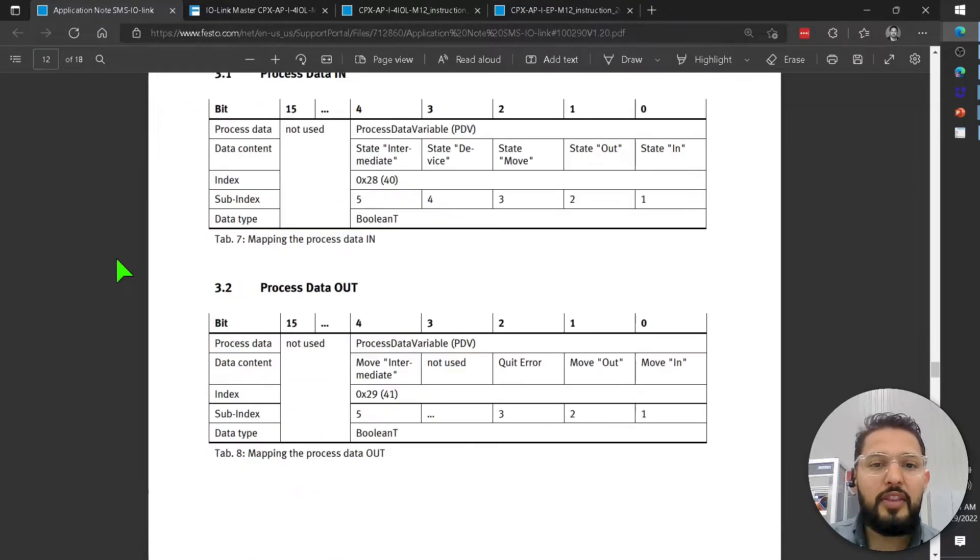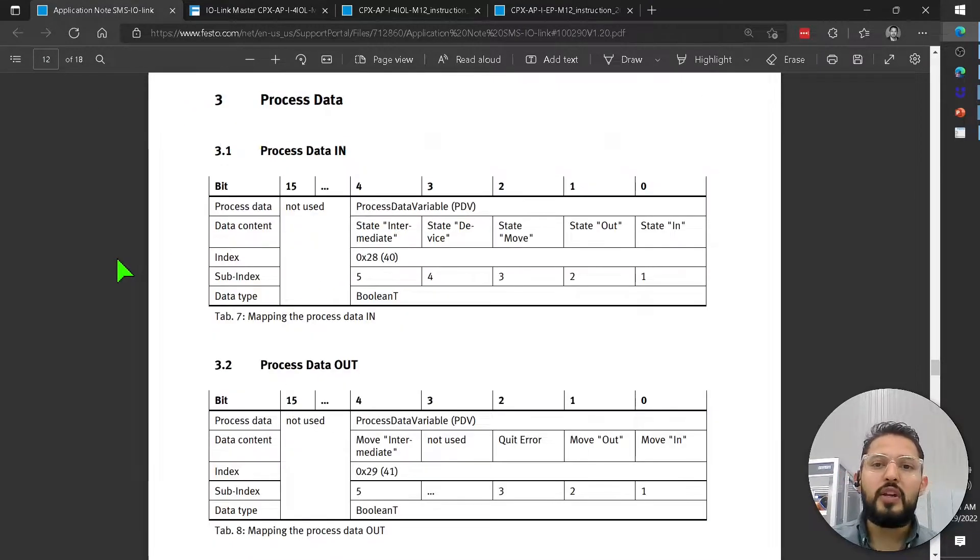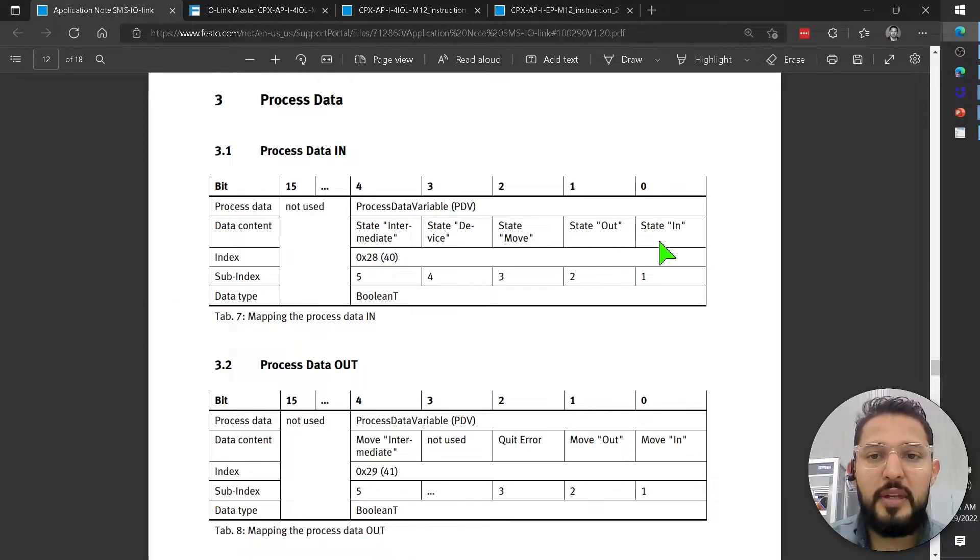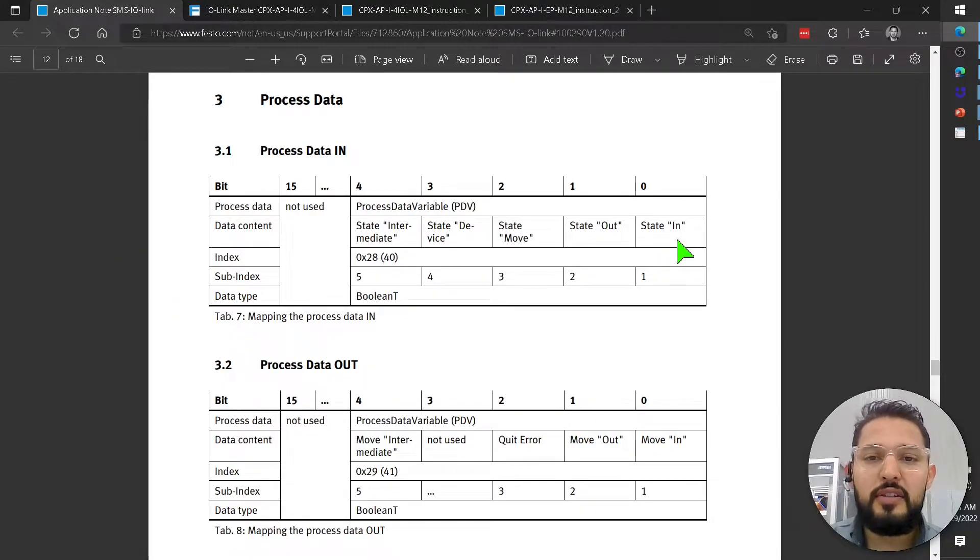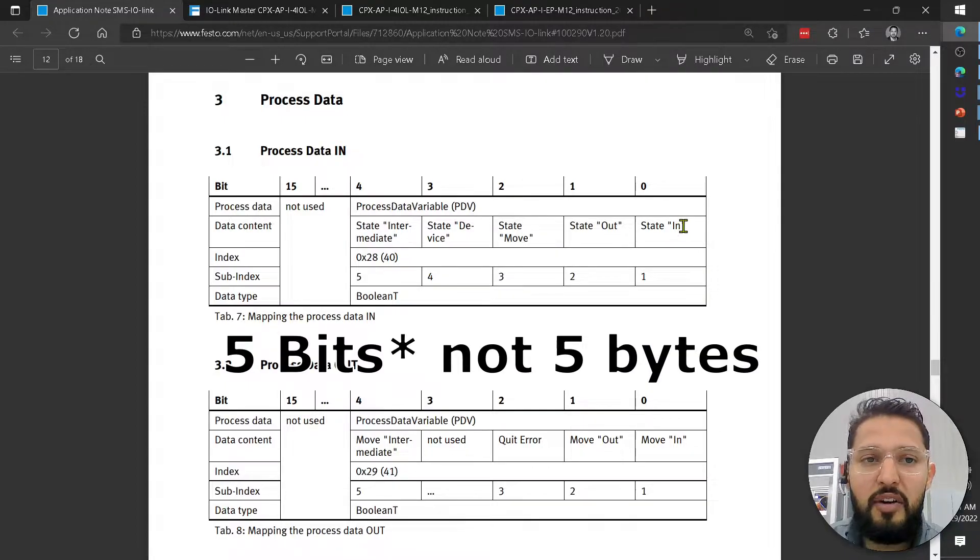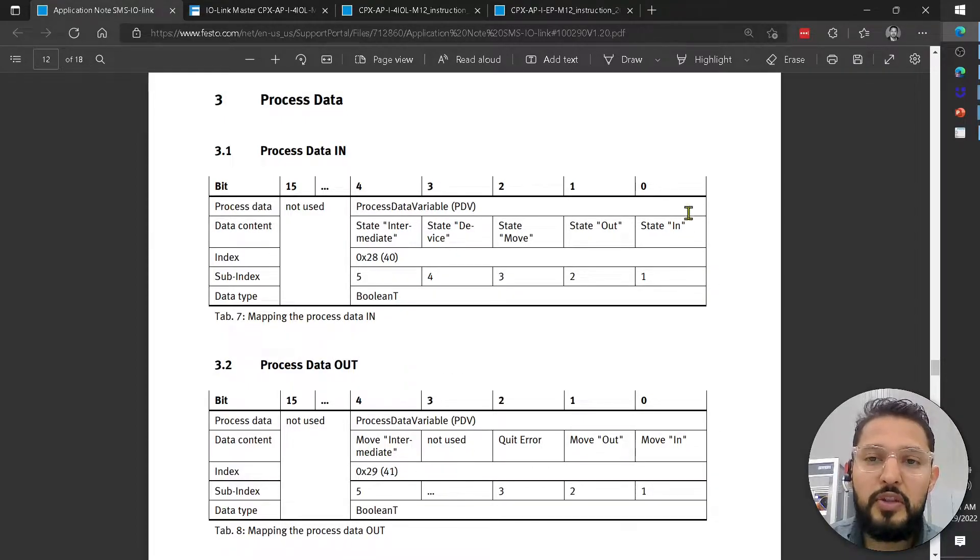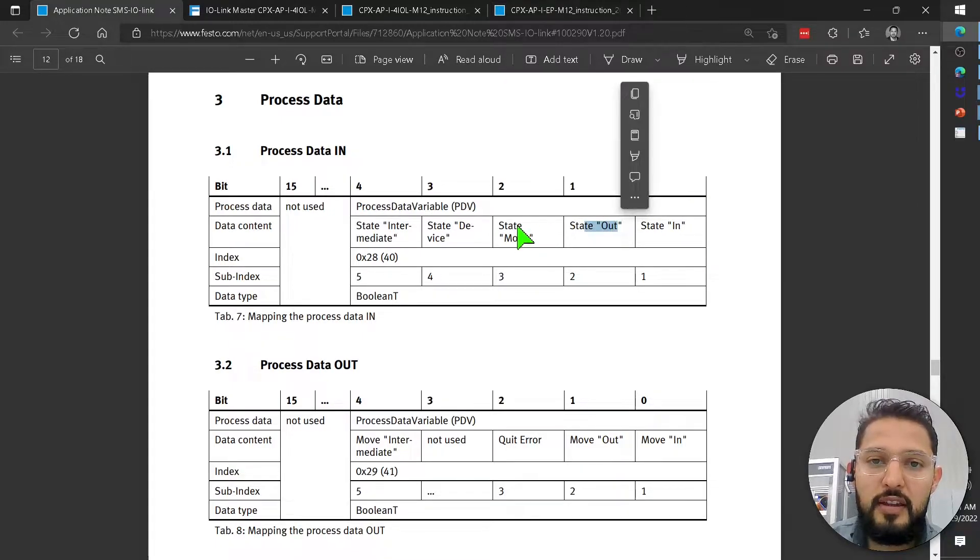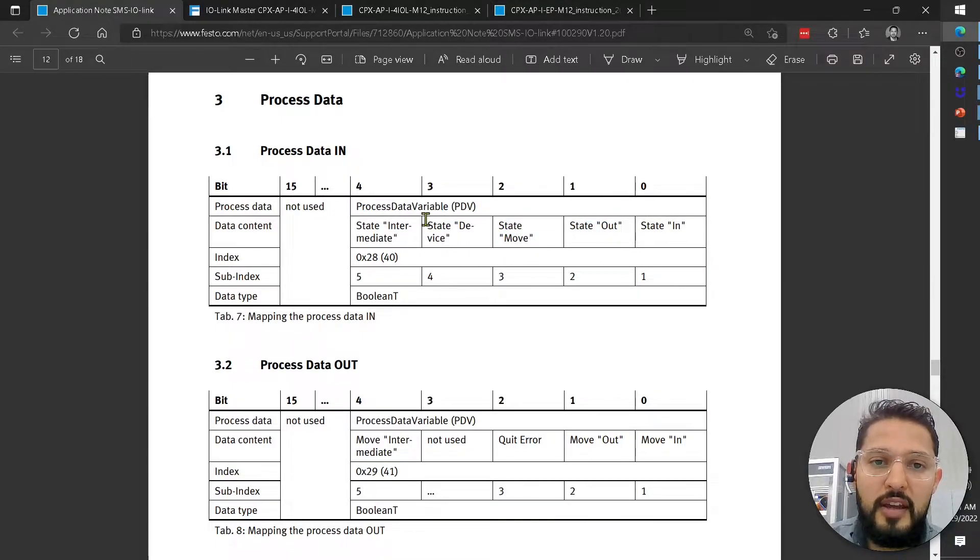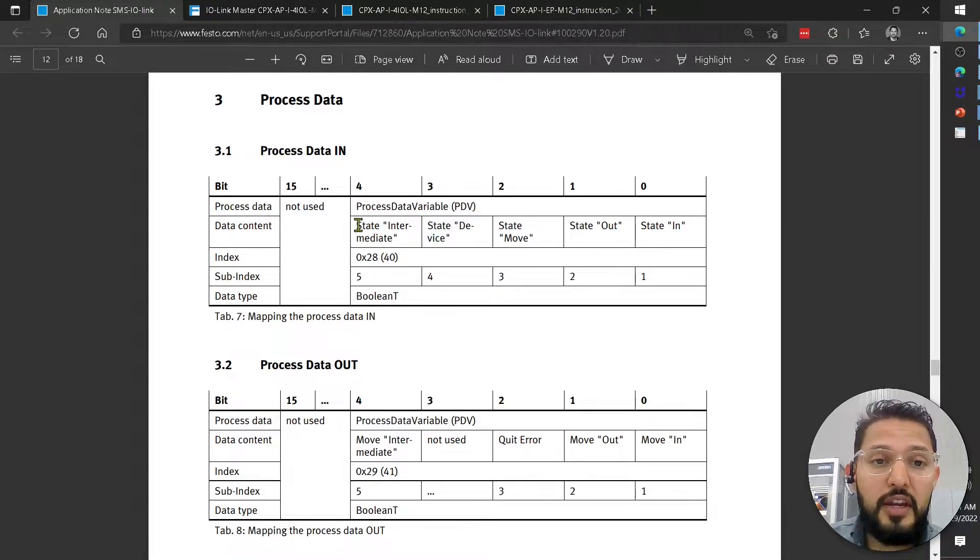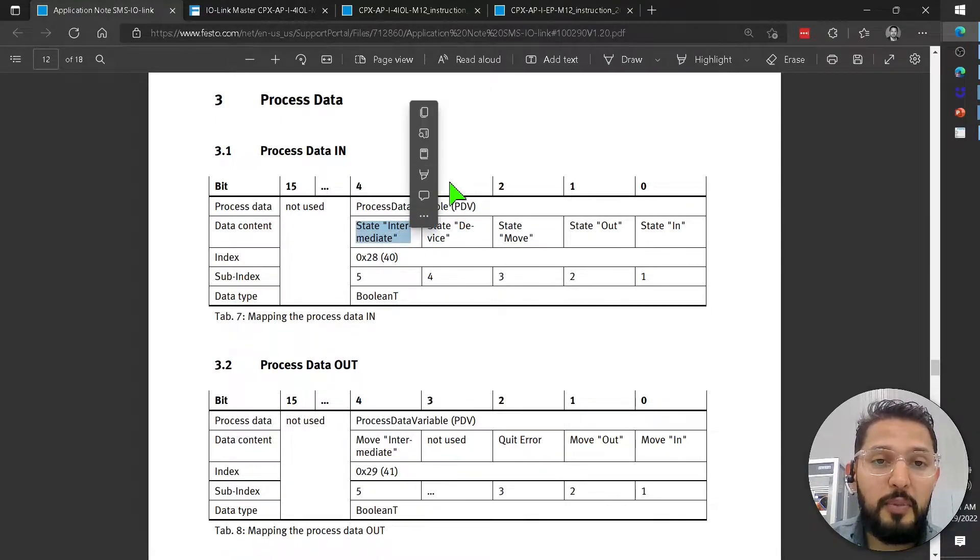Here I have the process data. So this process data tells me that the motor has just like five bits of inputs. One is going to tell me when it's retracted, extended, if it's moving, if it is present or enabled, and if it's at an intermediate position.